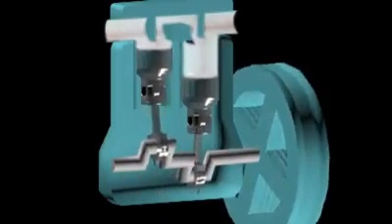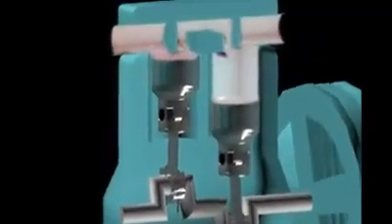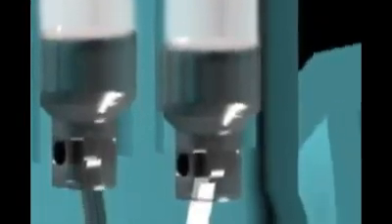The compression stroke will take place when the piston is moving upward. During the stroke, the pressure rises to slightly above the discharge pressure and will cause the plate-type discharge valve to open. The refrigerant passes through at approximately constant pressure and flows to the condenser. At the end of the stroke, the differential pressure across the valve, aided by the valve spring, will close the discharge valve and another suction stroke begins.